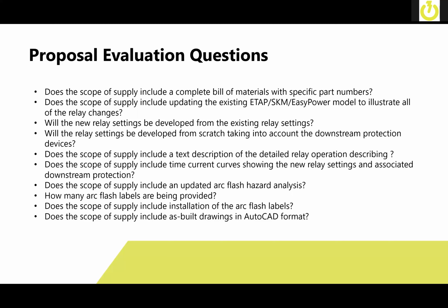How many arc flash labels are being provided? If you change the arc flash hazard analysis and have an updated arc flash incident energy, then a lot of times you'll also want to change your arc flash labels in the field. Does the scope of supply include the installation of those arc flash labels? If you're replacing 20, 30, 40 relays, you can have quite a significant amount of labels that need to be installed, depending on how the old protection was set up. And then finally, does the scope of supply include as-built drawings in an AutoCAD format, or are you just getting back a bunch of redline drawings?